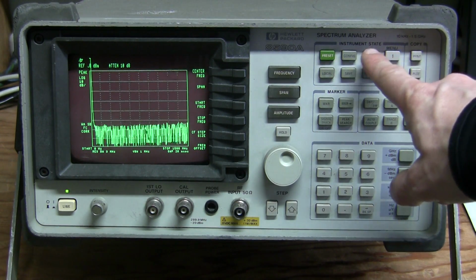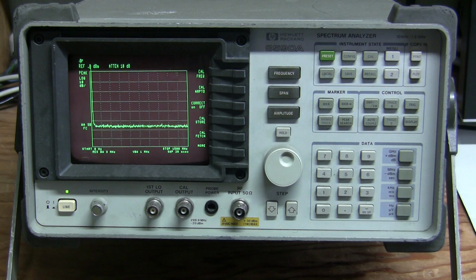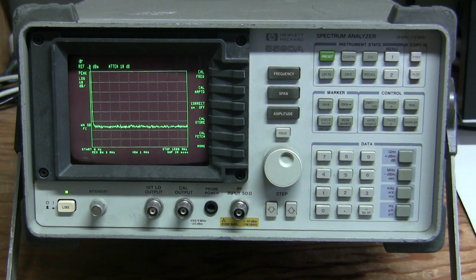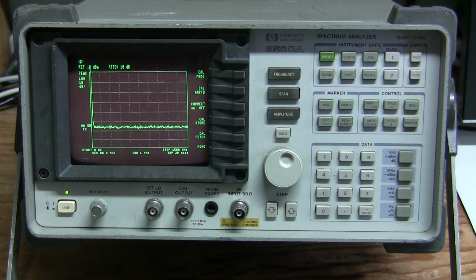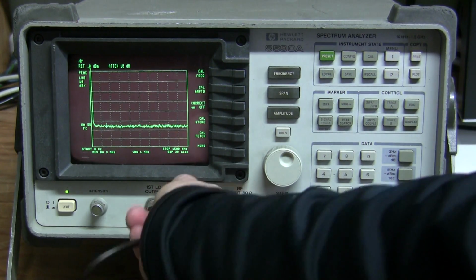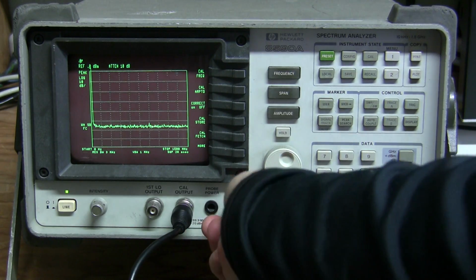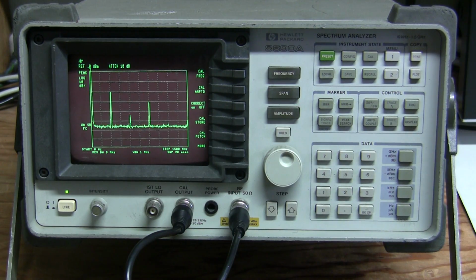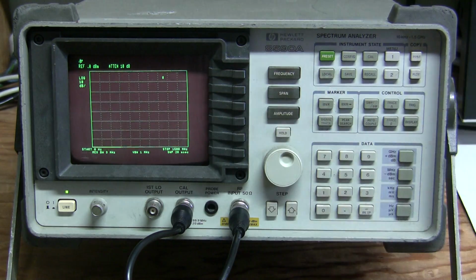With the correction off, the signal looks better. Probably a bit high noise floor. I found some pictures on the internet which show the noise floor one division below, but that might be with correction. So let's try running the self-calibration. To run the calibration, we need to connect the calibration output to the input. Well, looks fine on the first glance. So let's run this first frequency calibration.